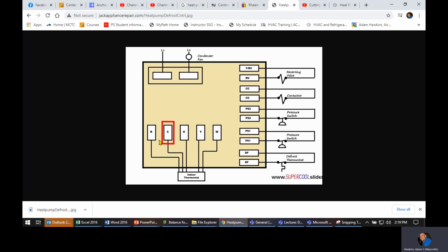So these three: red's getting power from the stat or from the transformer. Common is sending power back to the transformer, or neutral. Orange is getting power from the thermostat. So the thermostat is dictating, by the position that it's turned on, whether it's in cool or whether it's in heat, whether that orange needs to be energized or not energized. So as soon as you switch that to cool or heat, let's say, for example, that you switch it to cool, and on that particular system, cool is energized, so it gets 24 volts.